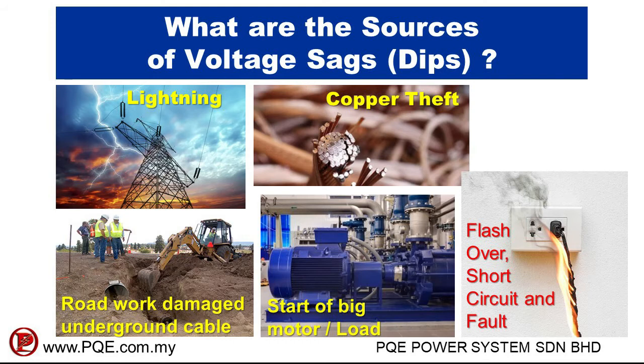What are the sources of voltage dip? Voltage dip could be caused by: lightning strike on the power lines; copper cable theft where someone cuts an in-service copper power cable; start of a big load on a power system causing an internal voltage dip; road work which accidentally damages underground cable; and flashover, short circuit, and fault.